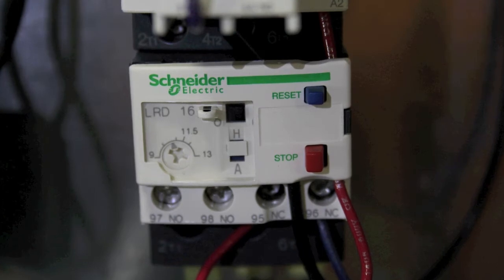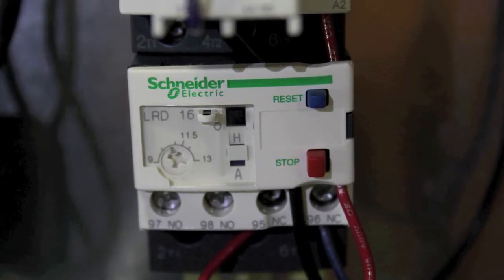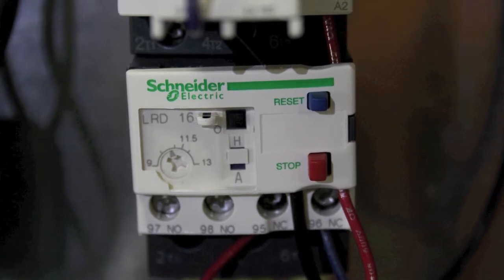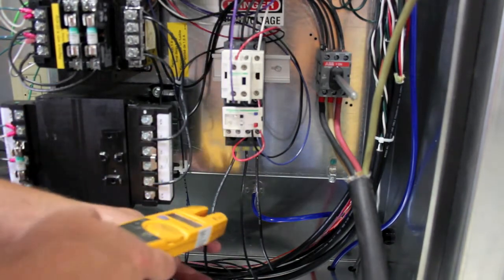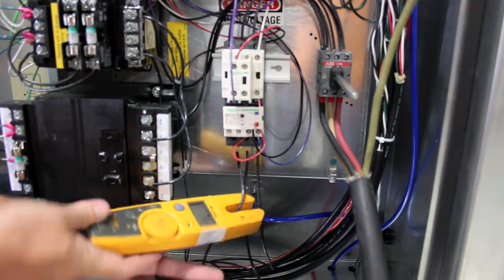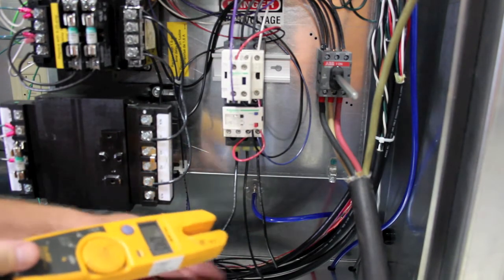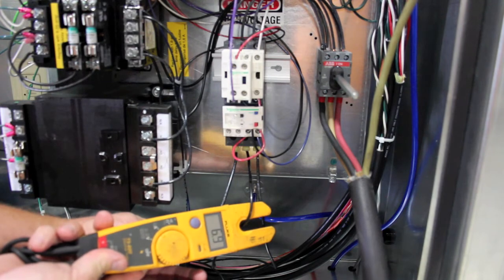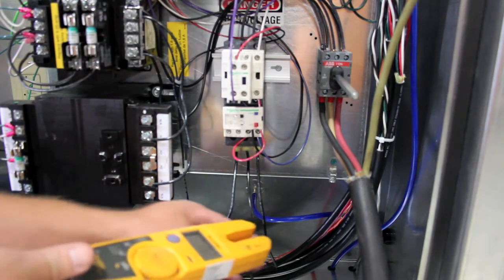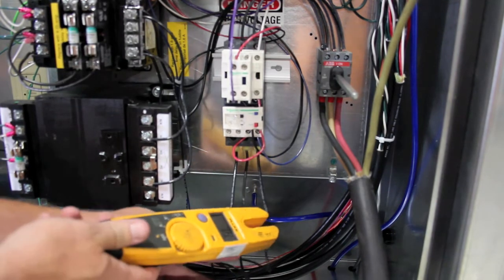Once your photohelic gauge is stabilized, verify your overload setting below your contactor. Once your photohelic is stabilized, you must now check your motor amp draw. There are three wires on the bottom of the overload. Be sure to check all three wires and average the amperages read. The amperages should not exceed the overload set point. If they do, please consult the factory.